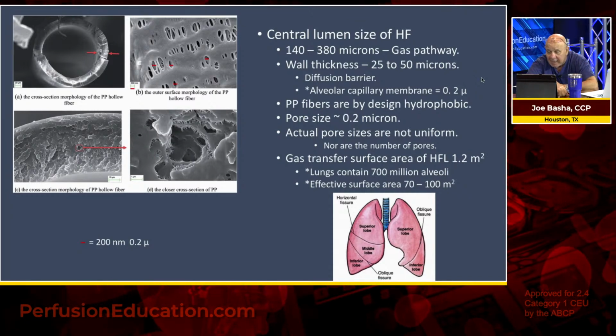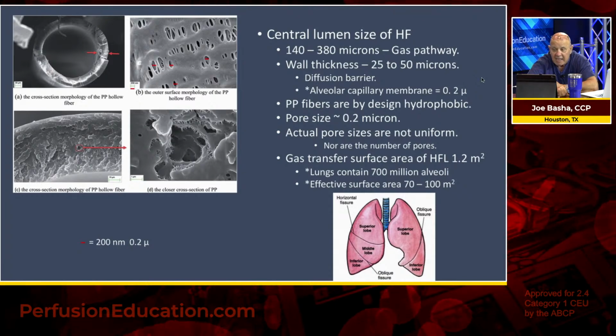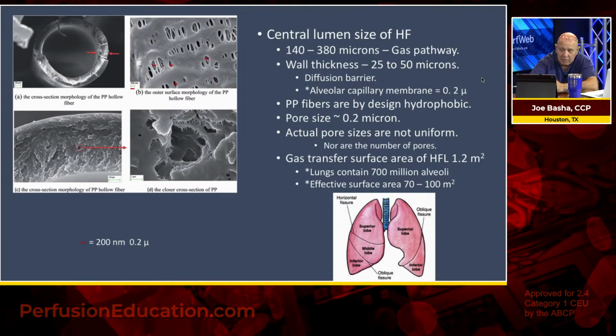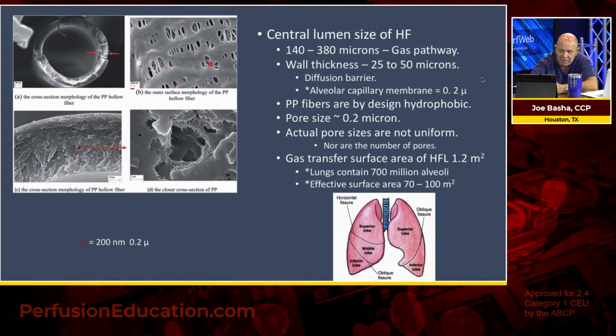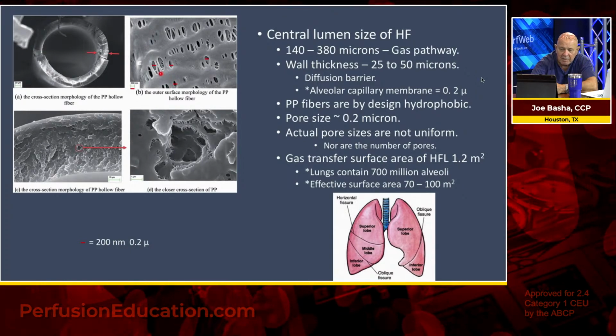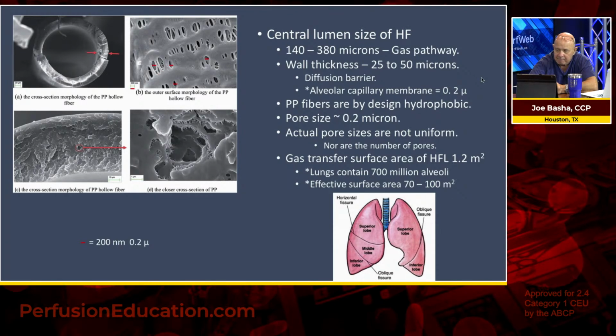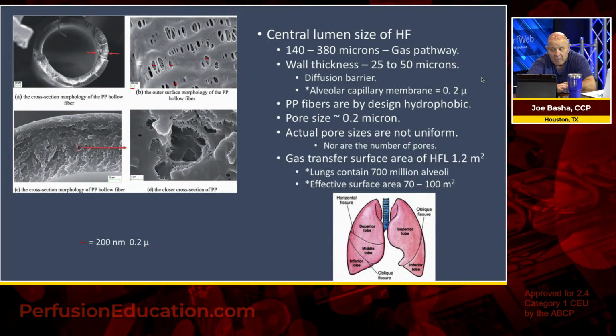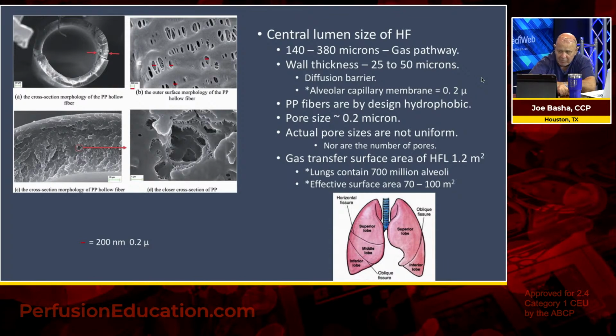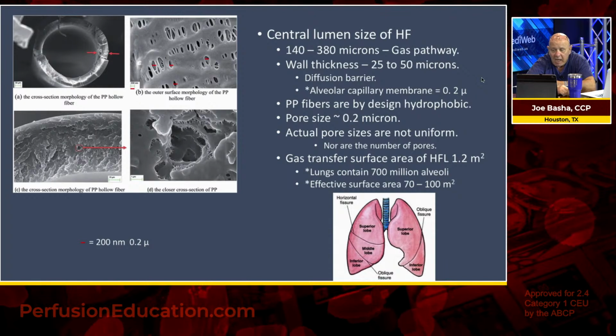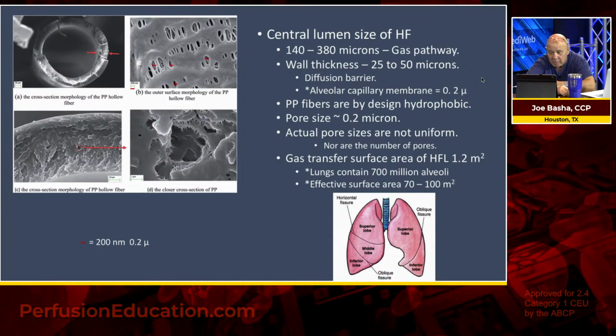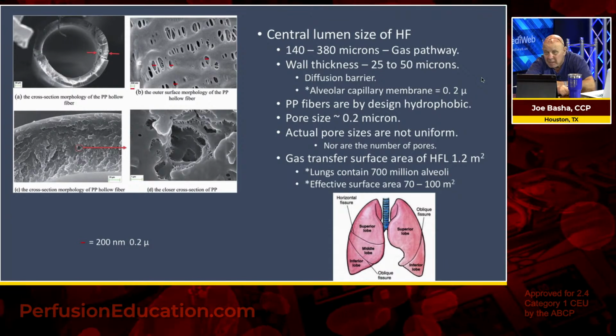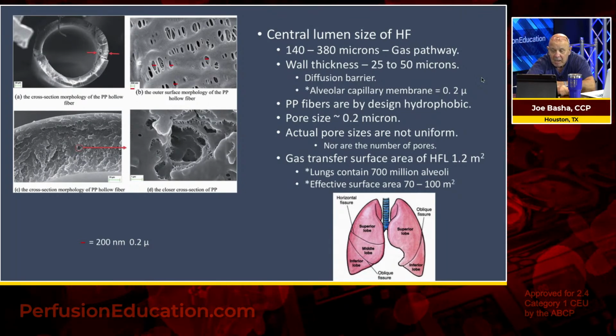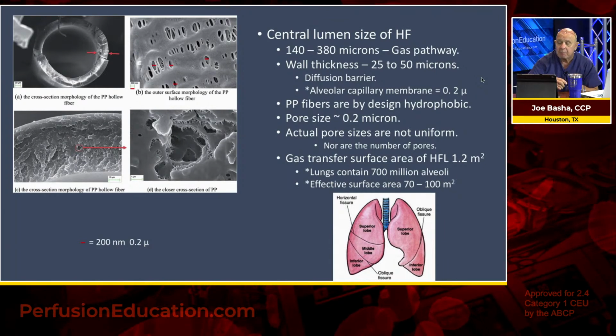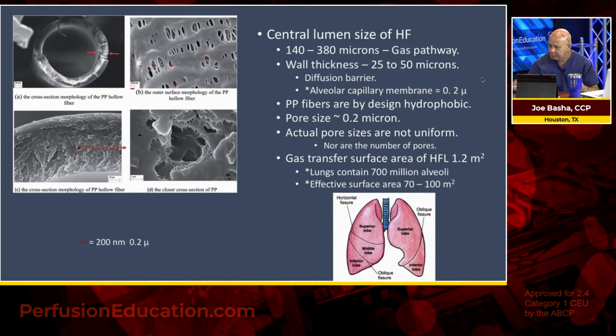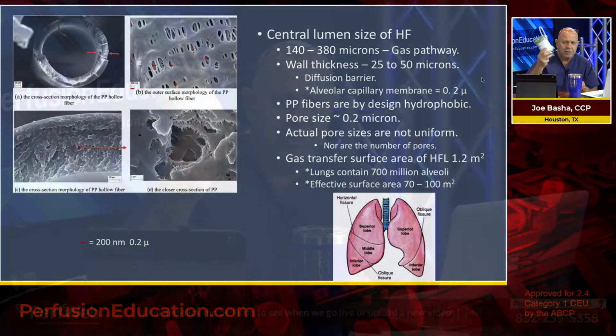Polypropylene fibers are by design hydrophobic, and they have a pore size of approximately 0.2 microns. I'm going to show a little more of a close-up, but if you look here on the right side, you see those little red lines. Those little red lines are 200 nanometers or 0.2 microns in size. The actual pore sizes, however, are not uniform, nor are the number of pores in any one, let's say, area. The gas transfer surface area of a typical hollow fiber lung is about 1.2 square meters. The lungs, on the other hand, contain 700 million alveoli and have an effective surface area of 70 to 100 meters squared.